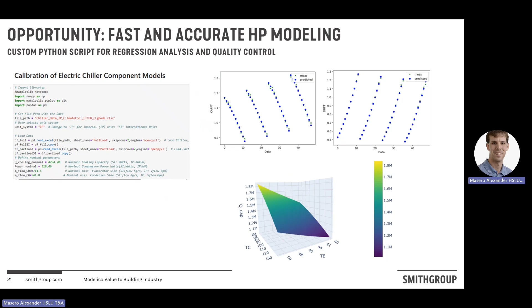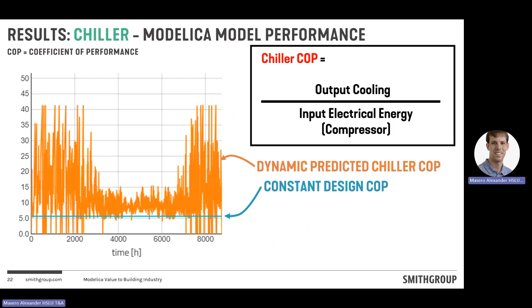But we're able to model the part load performance, and if you know chillers you might think a value like 40 doesn't seem right — usually we see 5 or 6 at most. But at part load, it's true. I was even second-guessing the data and confirmed it with the manufacturer: part load, magnetic bearing, low lift chillers have amazing performance. You should capture that when you simulate.